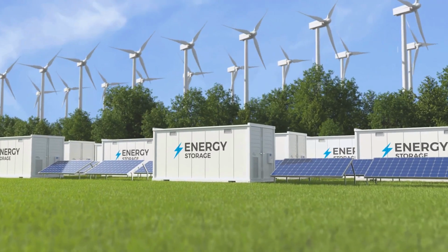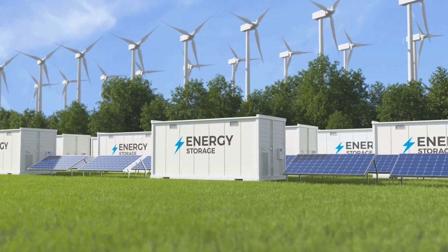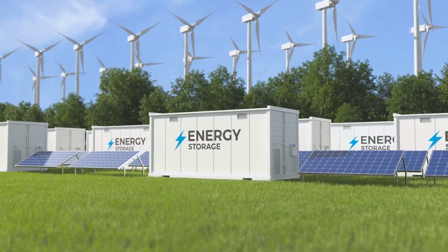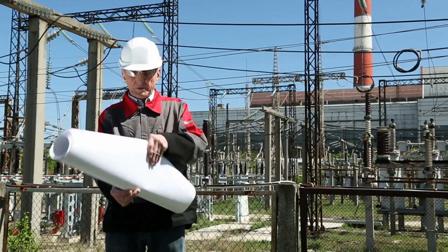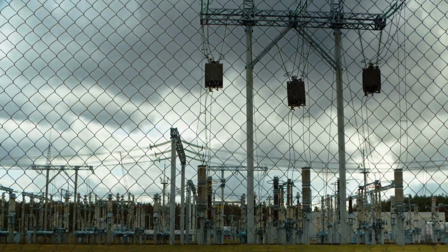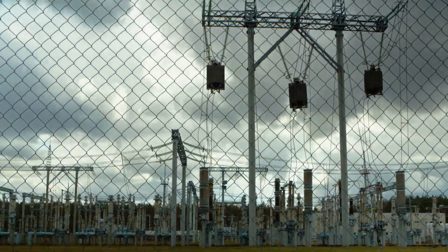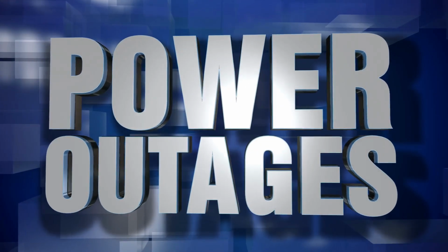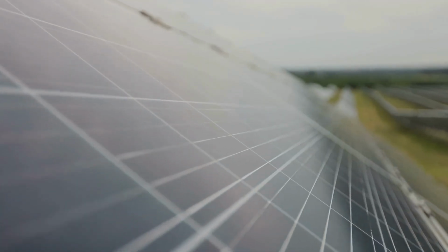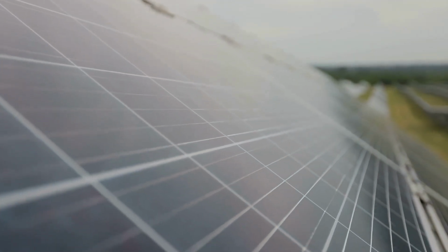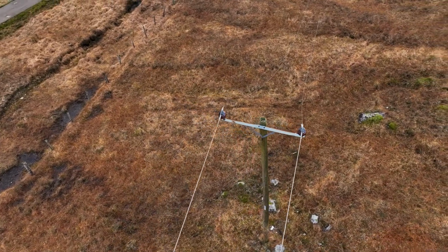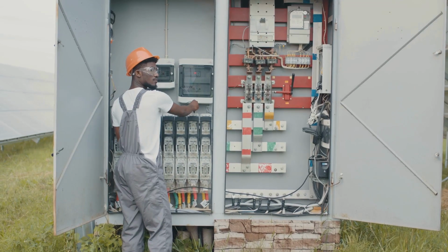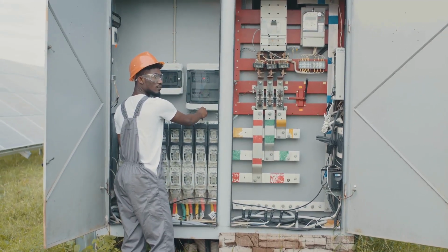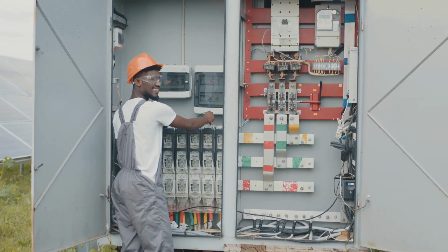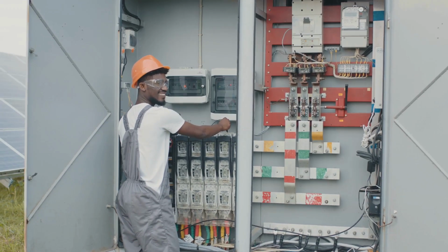The evolution. The 2018 update is transformational. It moves DERs from passive generators to active grid participants. From the fault ride-through standpoint, this shift is critical. In older versions of 1547, DERs were allowed, or even encouraged, to disconnect immediately at the first sign of a fault. But with increasing DER penetration, this approach creates instability. Imagine hundreds or thousands of DERs tripping offline simultaneously during a minor voltage sag. The result? Amplified grid collapse, load imbalance, and longer recovery. IEEE 1547-2018 now explicitly requires DERs to ride through most fault events, and Section 1 frames this as a systemic responsibility, not just a device feature.